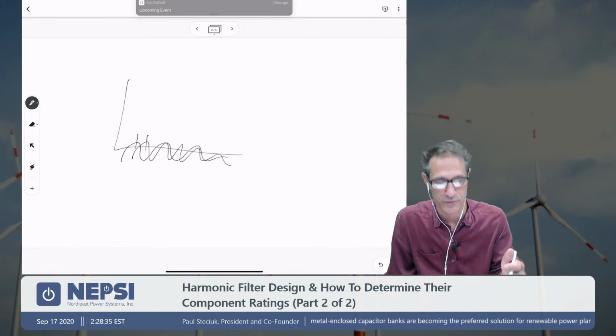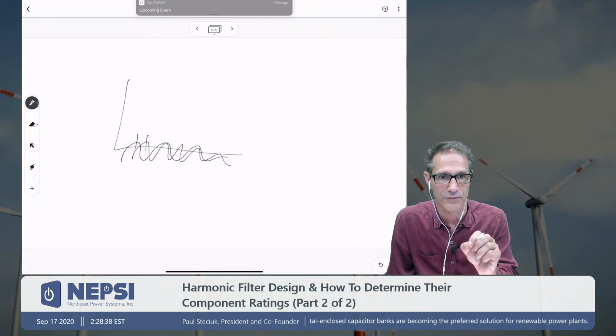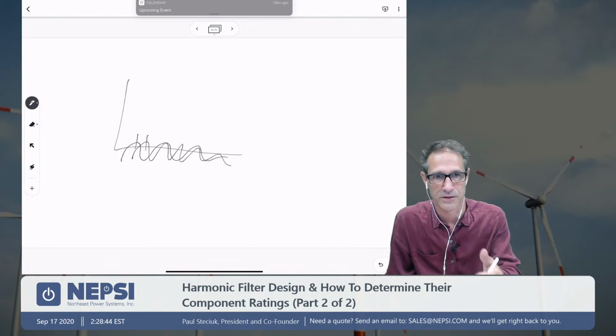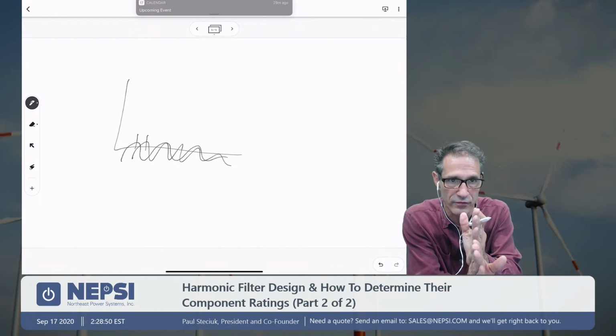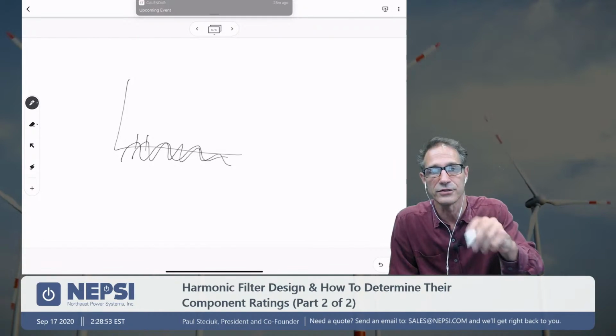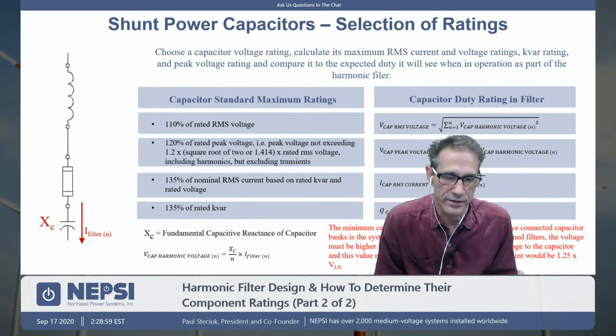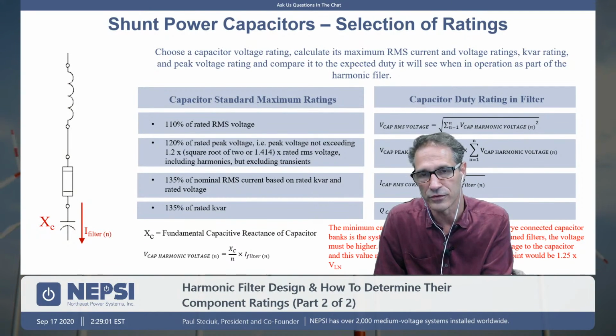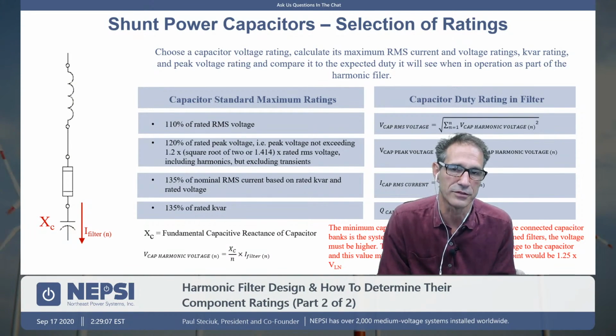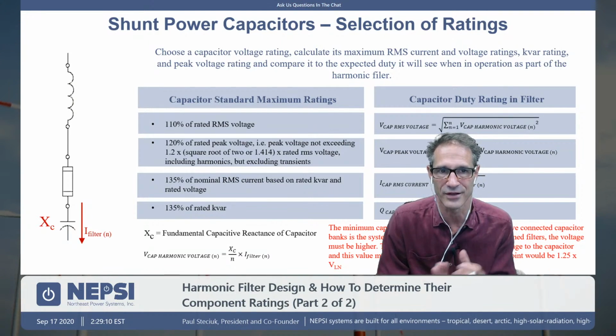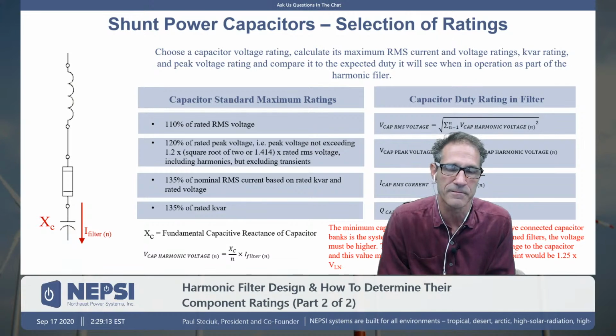So 5th, you calculate the 5th harmonic voltage, the 7th harmonic voltage, the 11th harmonic voltage. We're making an assumption that all the peak values of voltage are in line with each other. So the peak of the 5th, the peak of the 7th, the peak of the 11th, and so on, they're all in phase with each other, so the phase angles are the same, so that we get the worst case condition, we get the highest peak voltage. We're testing peak voltage, and incidentally, when you do harmonic filter design, generally peak voltage is the limiting factor. That's what we have found in most cases. Peak voltage determines the rating of the capacitor. Not always, but for most filter designs, that would be the case.